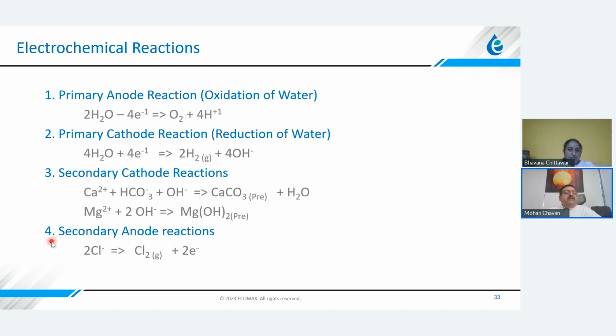And the fourth reaction is the secondary anode reaction, where chlorides, which have got negative charge, will be broken down into chlorine gas and electrons. So this chlorine gas will act as a biocide to kill the microbes. Along with the chlorine, H2O2 and O3 oxidants are also generated in the process, and that's where the process can be used to control the microbial count and algae formation inside the cooling towers.